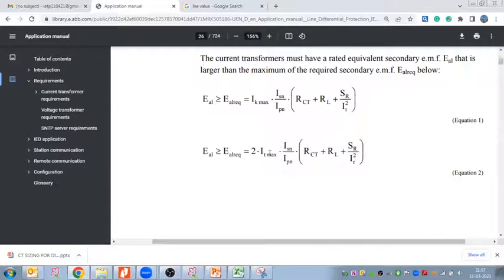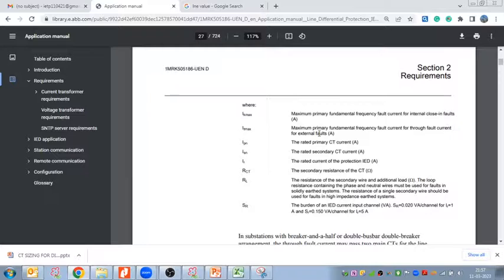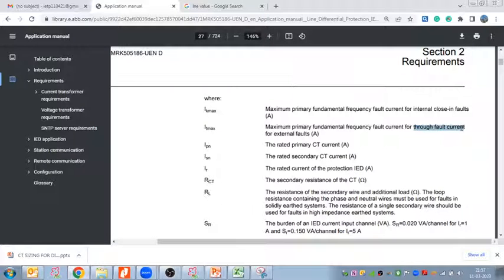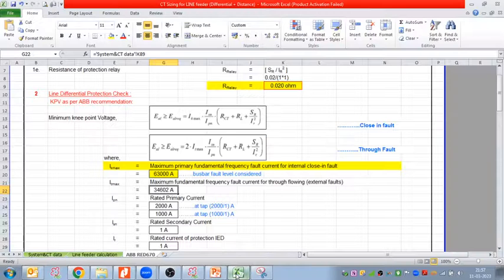So this is all we know. Now this IT max we wanted to calculate. IT max is the through fault current. For the through fault current, we are calculating the source resistance and impedance. Clear on why we have done the source resistance and source reactance calculations.